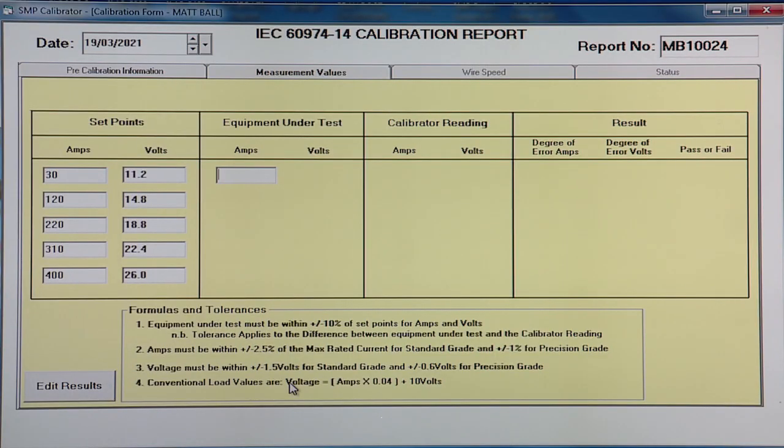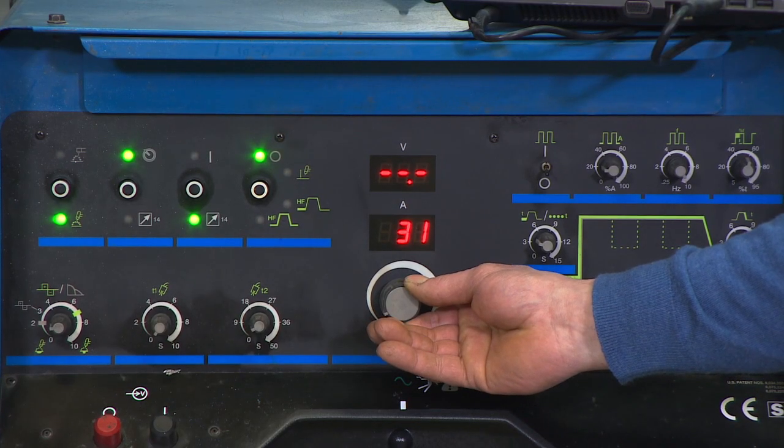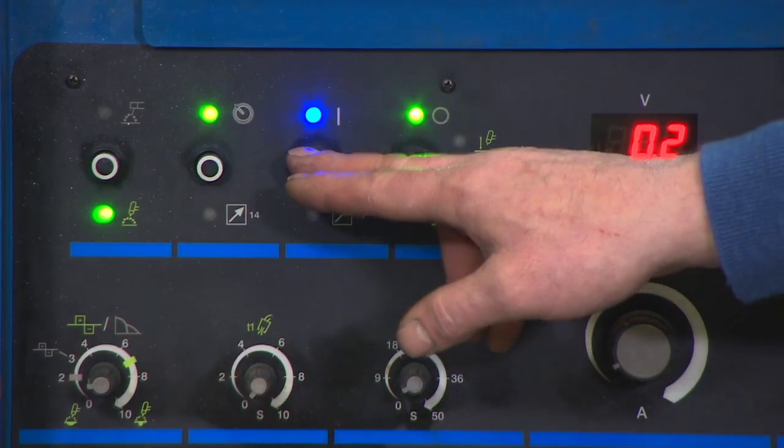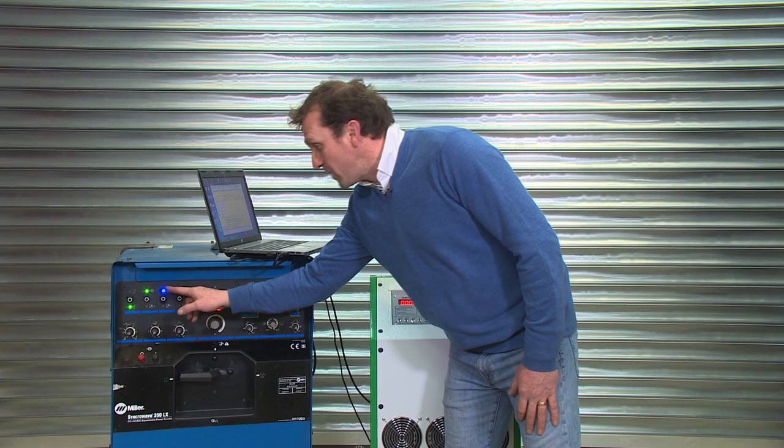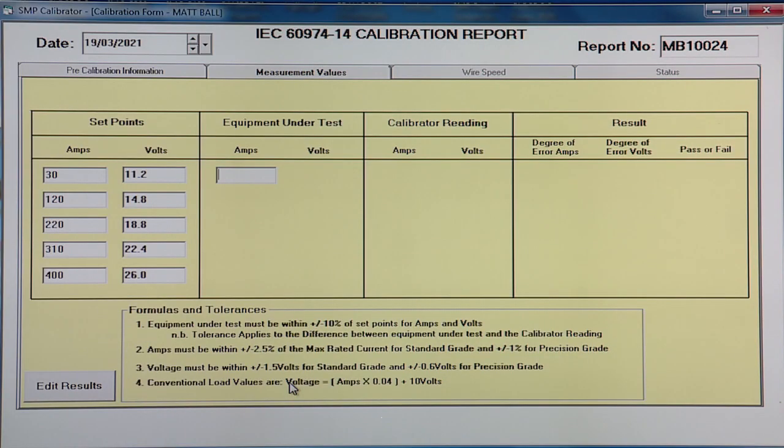Our first reading, our minimum reading, is 30 amps and 11.2 volts. So we set the amps at our first reading, 30 amps. We'll then energize the machine, turn it on, either from the front panel or using the TIG torch trigger. We're then going to load the welder to 30 amps, 11.2 volts within that 10% margin.